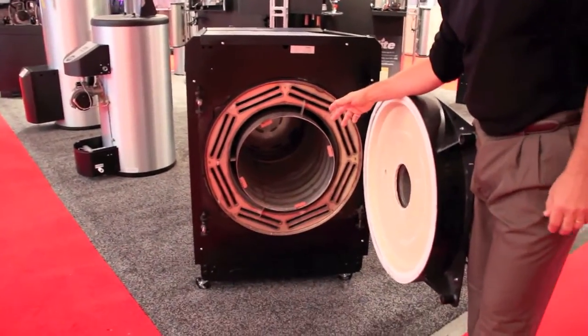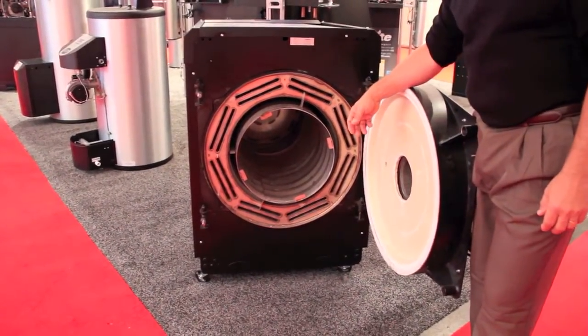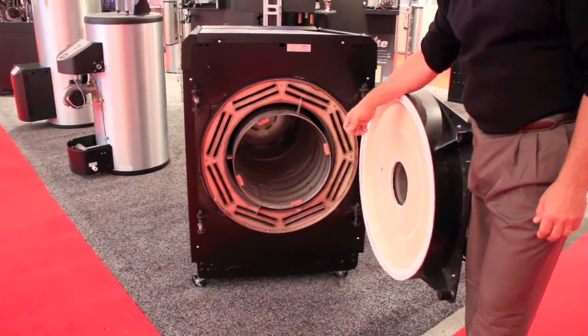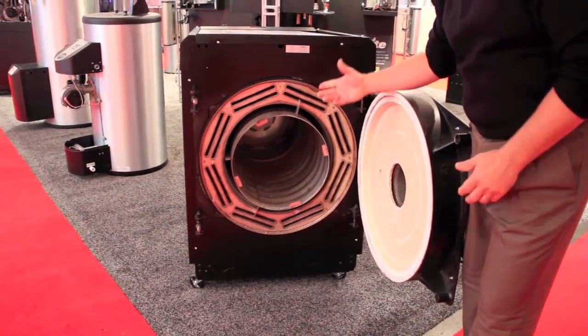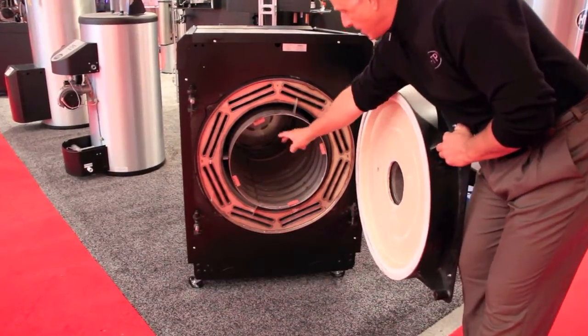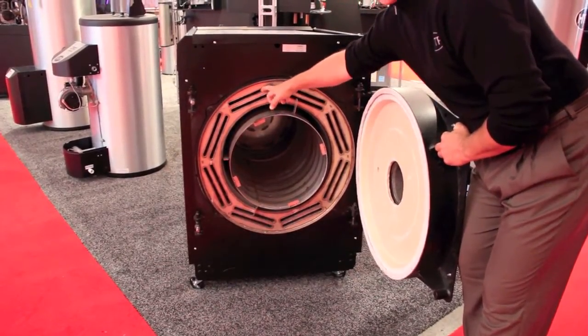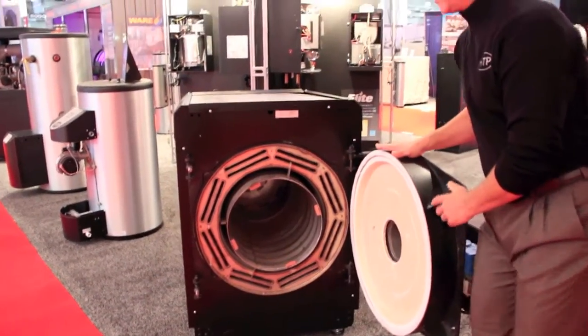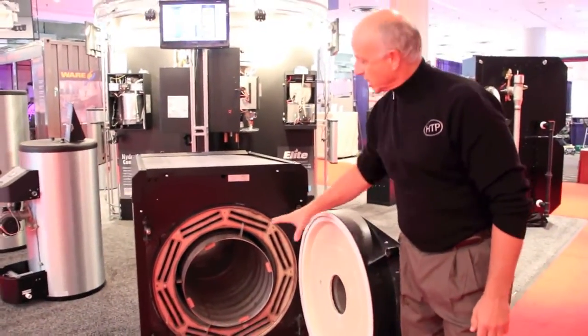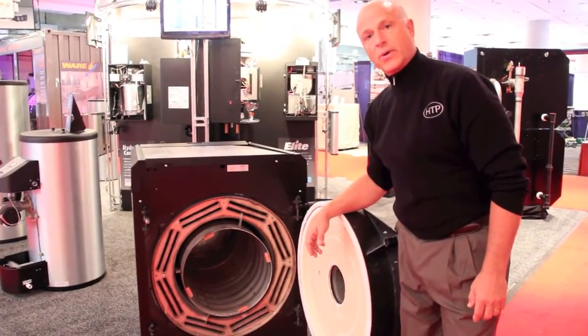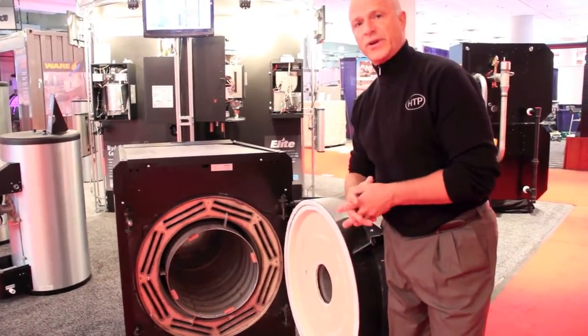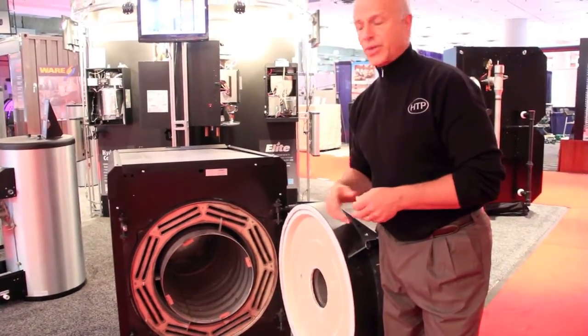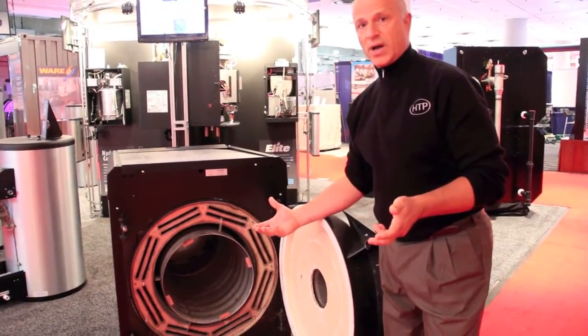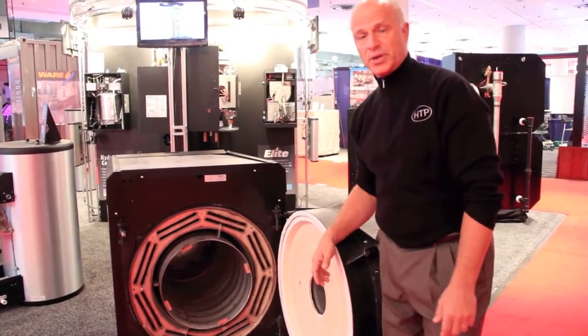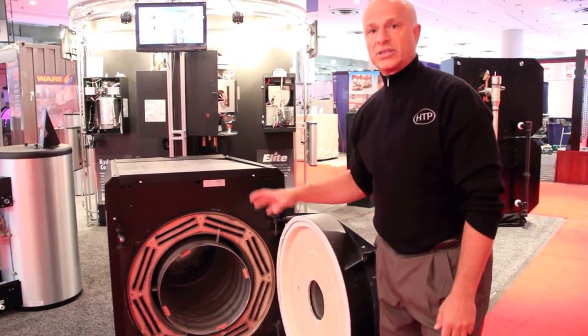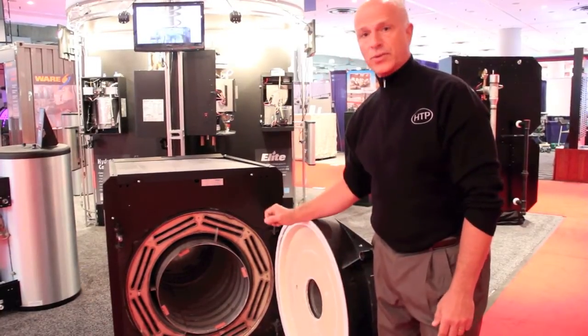The construction of this is made out of 316L Ti, a very high-grade titanium-based stabilized stainless steel. It's a triple pass where the flue gases go down the center, come back, and then go out the third pass here. Another real unique thing about this heat exchanger is that it allows us to go direct flow. So we can set them up in commercial buildings with variable speed pumps, either going primary-secondary if you want to, with a storage tank and hydraulic separation, or you can go direct. It has such low pressure drop that you can have direct flow right through the boiler.